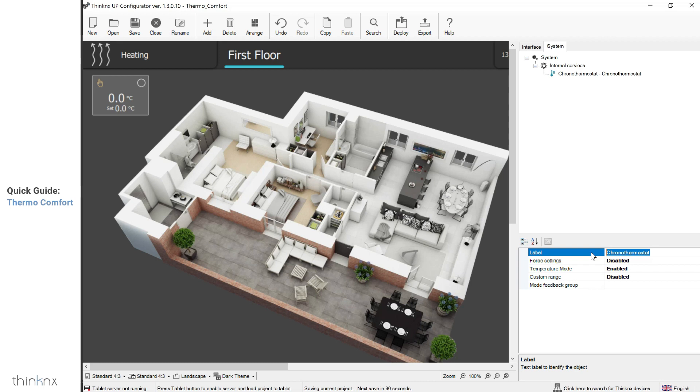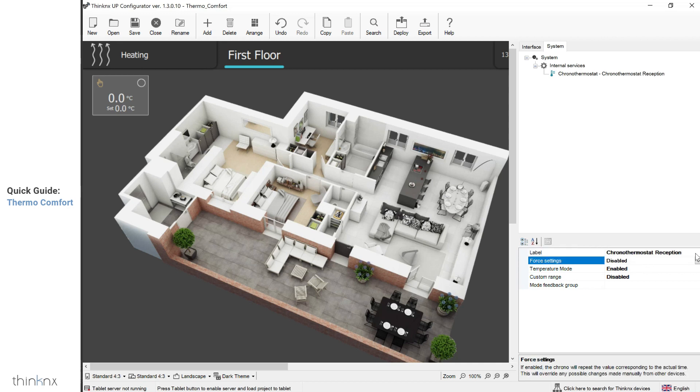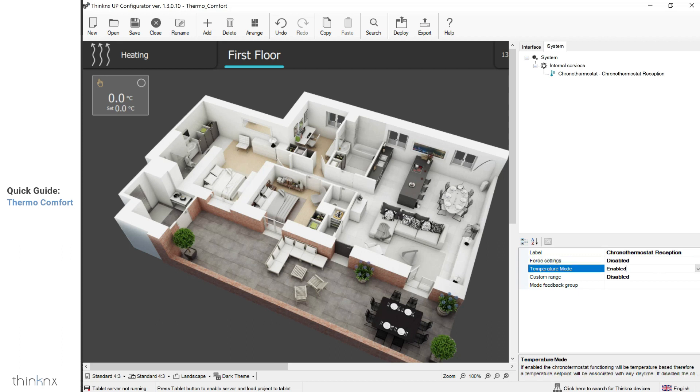In the properties, rename your object. If you want the schedule to override changes which are made manually by other devices, enable the force settings. When enabling the temperature mode, the schedule will be temperature based. If disabled, the schedule will be mode based.